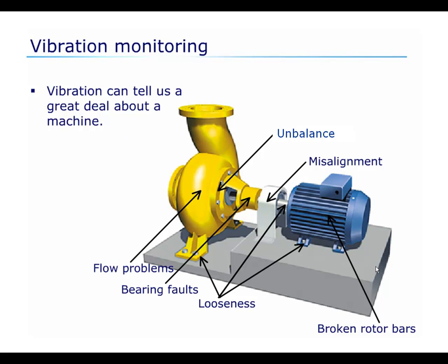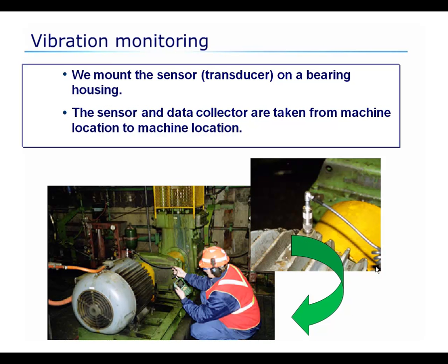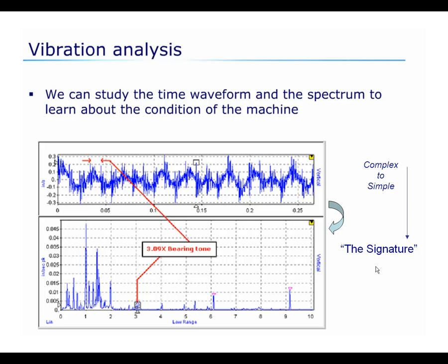Vibration monitoring can tell us a lot about the machine, from flow problems to bearing faults to looseness, unbalance, misalignment, and even electrical faults like broken rotor bars. Typically, we mount the sensor or transducer on a bearing housing to get the best mechanical interface, and the sensor and data collector are then taken from machine location to machine location. We study the time waveform — that's the raw signal that comes in from the accelerometer. It takes a very experienced analyst to look at a time waveform and deduce what might be the machine problems. So typically, we go from complex to simple and convert the time waveform to a pattern or a signature — FFT, fast Fourier transform, as shown here — and then we look for certain fault frequencies that will help us pinpoint the problem.